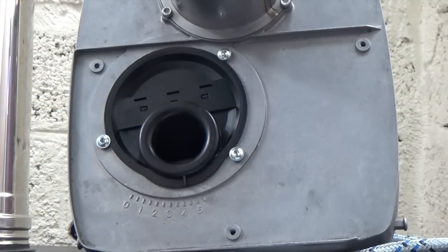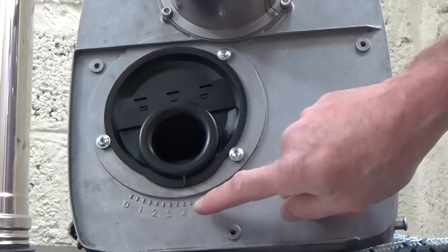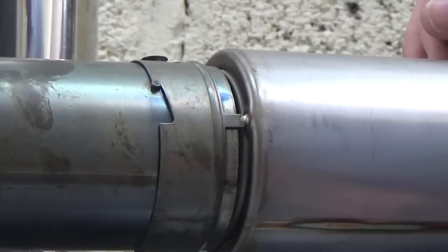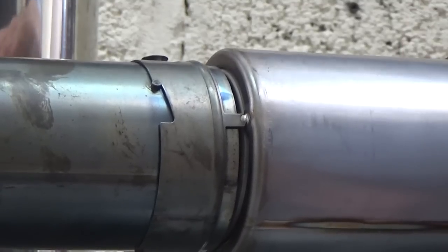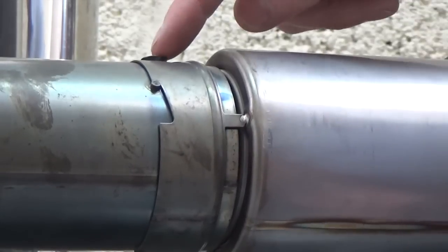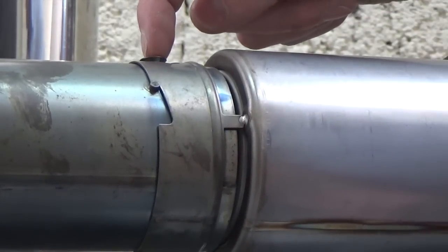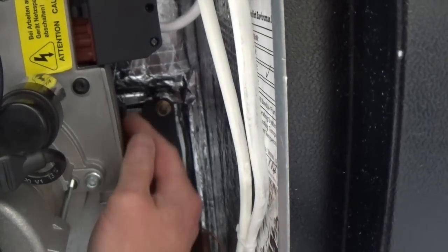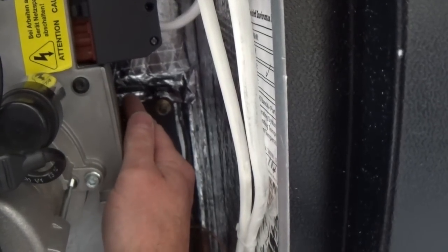Commissioning the boiler is a fairly simple process. Air for combustion underneath the air cover is preset at the factory at a setting of 4.5. The setting for recirculating the gases back through the blast tube will also be preset, and locked in position 1 at the factory. Any adjustment is made from the knurled handle set at the side of the airbox.